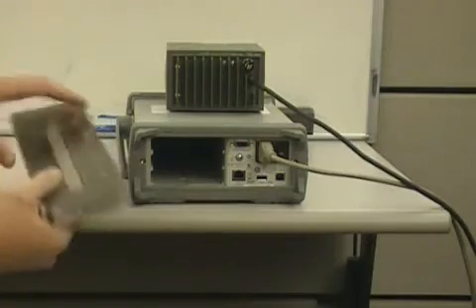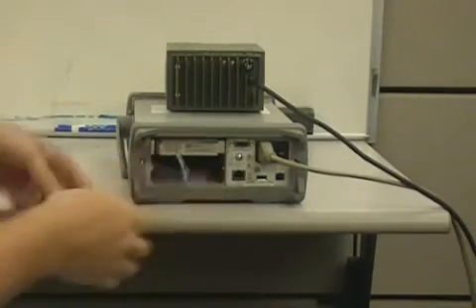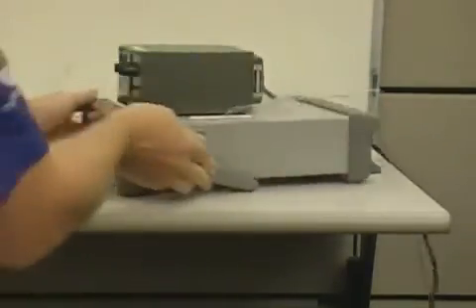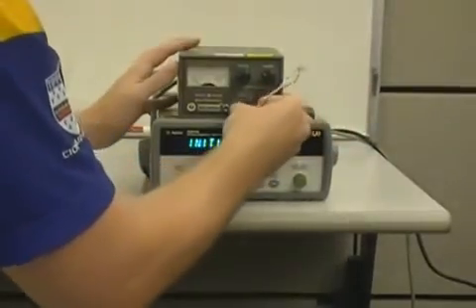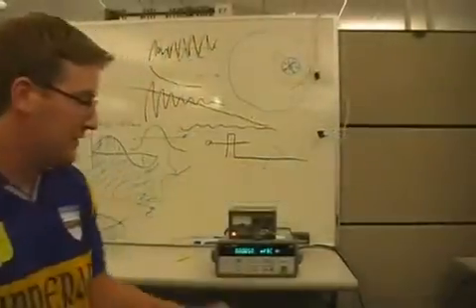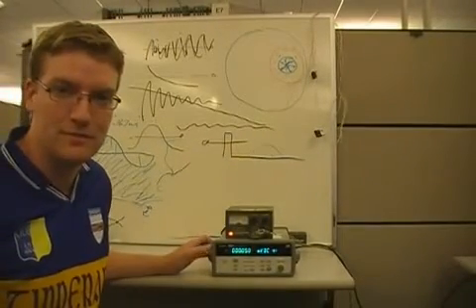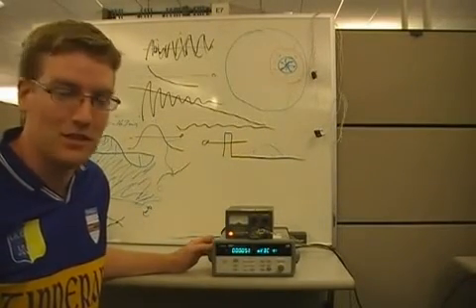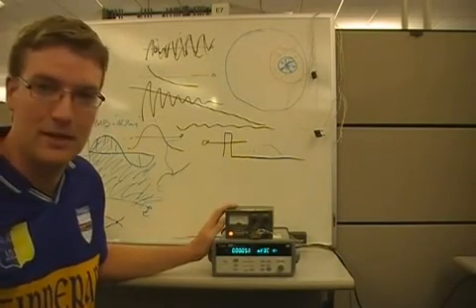Now we'll slide our card back into the 34972. Plug in our connection. Turn on the power supply. Now we can take the voltage displayed by the 34972 divided by the resistance of our shunt, and we'll get the output current of the power supply. In this case, 100 milliamps.